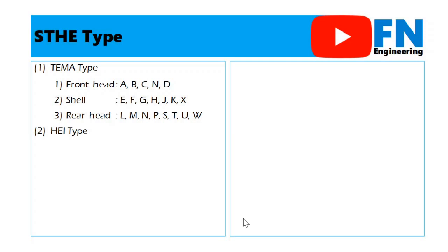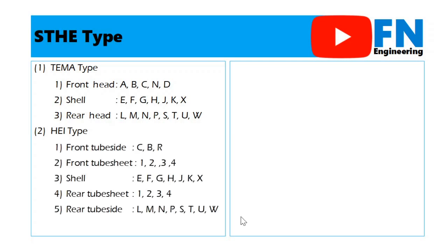The next type is HEI type. HEI type has 5 different configurations of shell and tube heat exchanger that are front tube side, front tubesheet, shell, rear tubesheet and rear tube side. Front tube side has 3 types. There are type C, type B and type R. Next, front and rear tubesheet have 4 types: 1, 2, 3 and 4. Shell type and rear tube side are the same as the TEMA design.